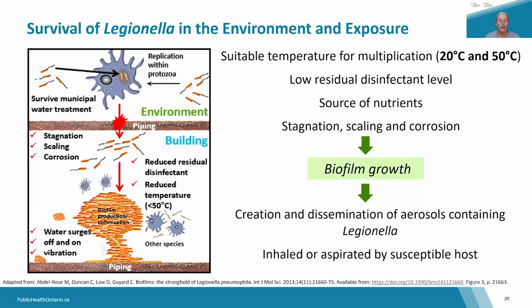conditions for growth. These conditions include a suitable temperature for multiplication, and ideal temperatures for Legionella growth are between about 20 to 50 degrees Celsius. A lack of chemical disinfection levels, such as chlorine, a source of nutrients, which can be from organic matter or iron in the plumbing. Also, the stagnation of water or any scaling and corrosion within the water system.